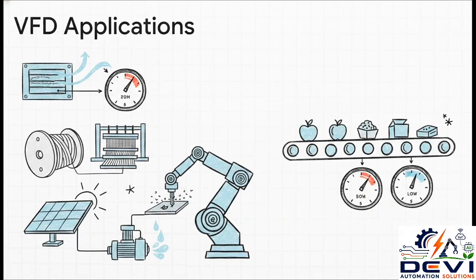grid. But, and this is a big but, when continuous speed control and energy management are required, VFDs are absolutely essential. Take HVAC systems, where airflow literally needs to adjust based on the room temperature, or textile industries, where thread tension requires ultra-precise speed adjustments. They're also crucial for CNC machines, food processing lines, and even smart agriculture using solar pumps, where the motor speed has to adapt dynamically to how much sunlight is available. In those scenarios, a VFD pays for itself in energy savings super quickly.